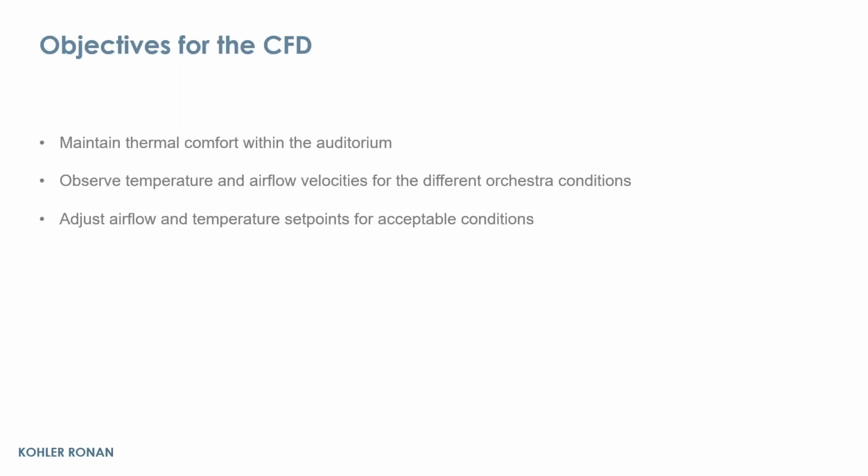We tested lots of different configurations, but the final testing happened on site. A lot of testing and balancing happened to make sure the airflow was coming out properly. But using the CFD software, Simscale, really allowed us to test all these different ideas and come up with at least a few ways to start our on-site testing.